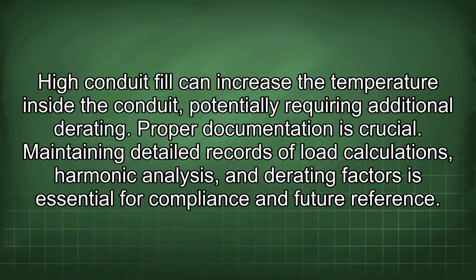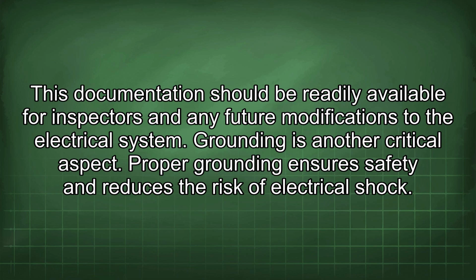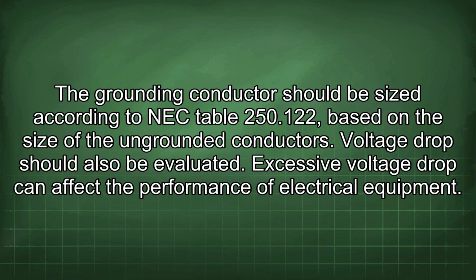Proper documentation is crucial. Maintaining detailed records of load calculations, harmonic analysis, and derating factors is essential for compliance and future reference. This documentation should be readily available for inspectors and any future modifications to the electrical system. Grounding is another critical aspect. Proper grounding ensures safety and reduces the risk of electrical shock. The grounding conductor should be sized according to NEC Table 250.122 based on the size of the ungrounded conductors.